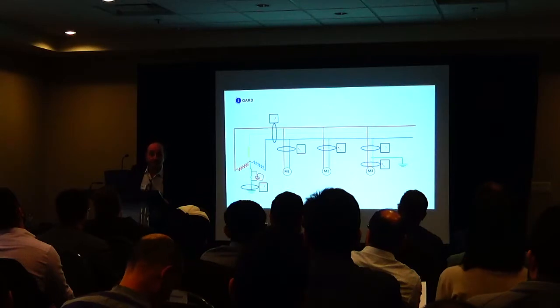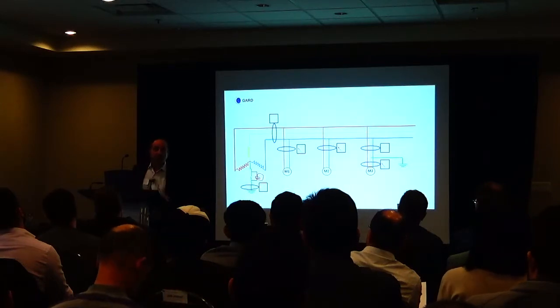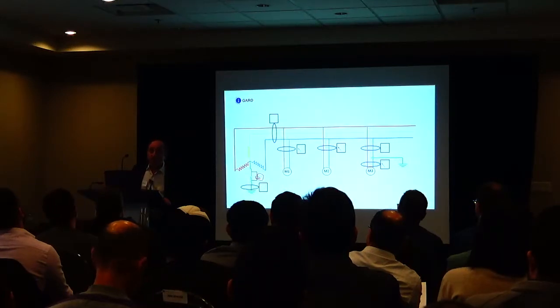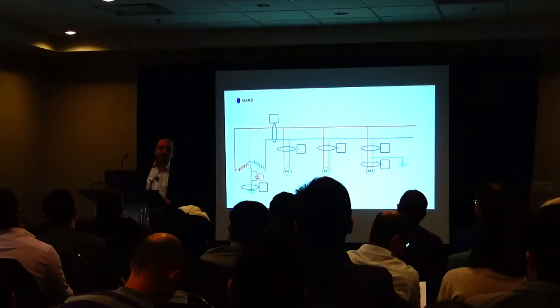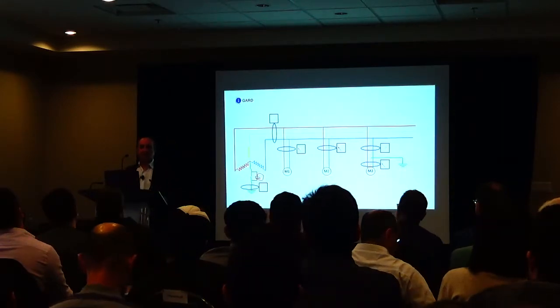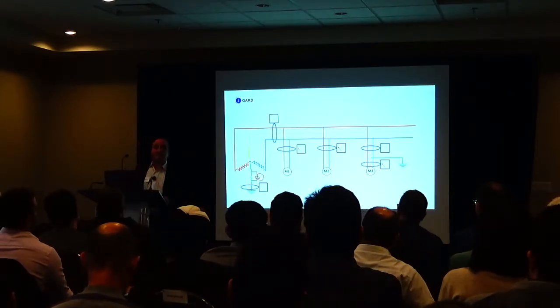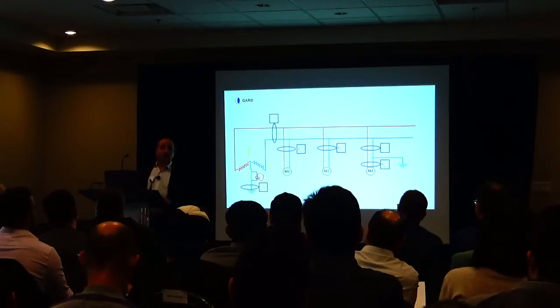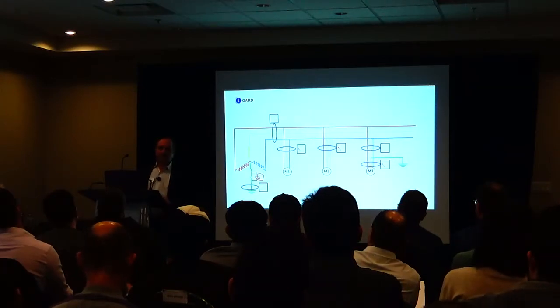So that G function would be kind of equivalent to the cost of the sensor? The G function is useless because we're limiting the fault current to 5 amps. Cost-wise, would it be comparable to a sensor that you install on one of these? Oh, more than comparable. How many feeders are you looking at? Depends. Even 2 feeders, it's very comparable.